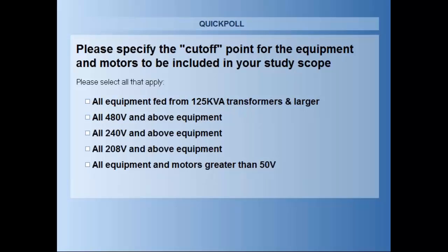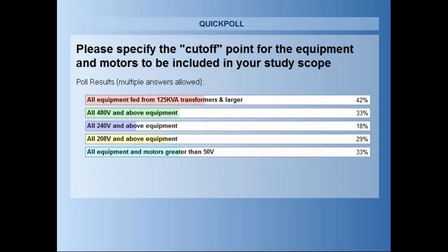Okay, we'll close that. Kind of mixed, I'd say — a cross between 480 and above, to anything fed from a 125 transformer or larger, to anything greater than 50. This is a perfect example of how critical it is, when writing an RFP, to specify what that cutoff is. That poll clearly shows how wide a range you may get when asking someone to quote-unquote do an arc flash risk assessment without specifying it.